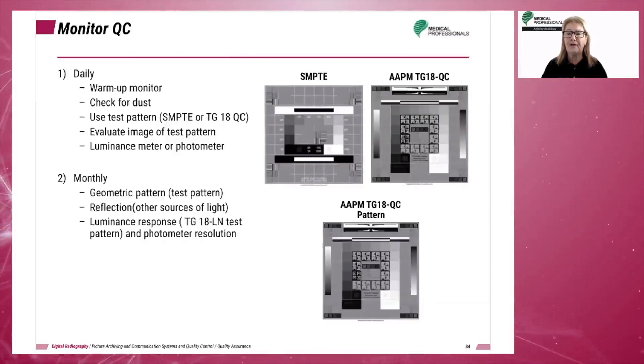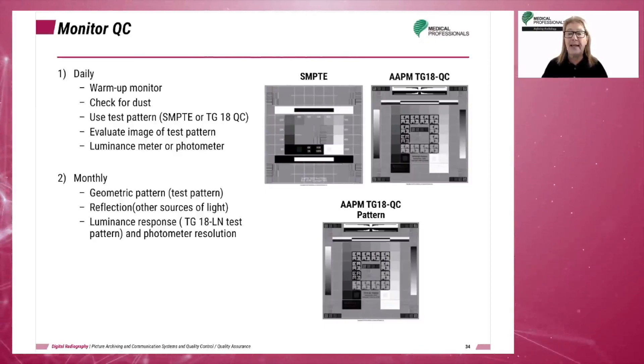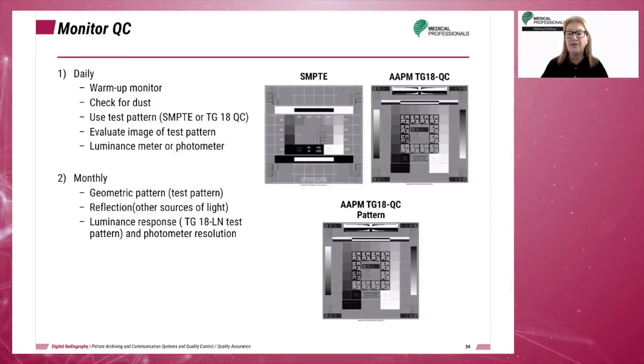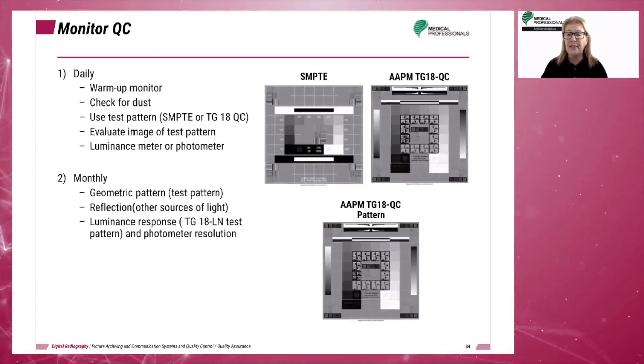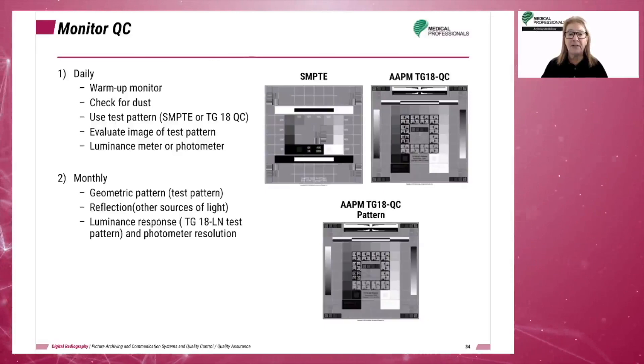According to Carter and Veal, the monitor should be turned on and given time to warm up before proceeding with the test. Check all areas of the monitor for dust and clean if necessary. Using either the SMPTE test pattern or the AAPM Task Group 18 test pattern, evaluate the image of the test pattern for overall image appearance, noting any non-uniformities or artifacts.